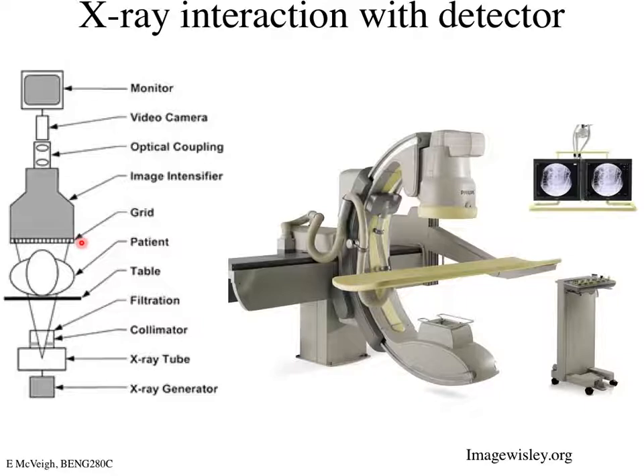The reason it's called a fluoroscope is because detection was originally via fluorescence. Nowadays this detector is usually a solid-state x-ray detector. Making one of these work beside an MRI scanner was an interesting project about 15 years ago, because the MRI magnetic field bent the path of electrons hitting the fluoroscopy unit, distorting the image.